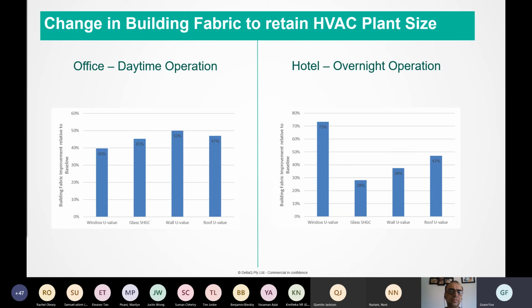And what this Camel exercise found was that in order to retain the same HVAC plant size in 2050, we would need to improve, when I say improve, I mean reduce our window U values, our glass SHGC, solar heat gain coefficient, our walls U value and roof U values. So we need to decrease them by between 40 to 50%, so improve double the performance in an office building or daytime only building. And roughly similar for hotel, except for window U value, which becomes increasingly important in an overnight building. So that's significant because it tells us that just using a different climate file or considering what a future climate looks like would change our HVAC plant sizing significantly.